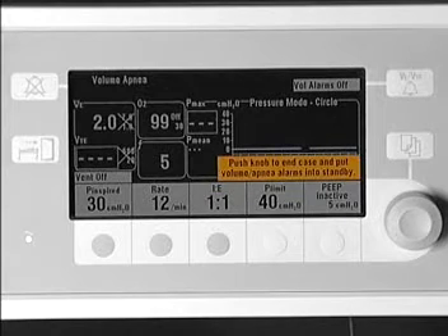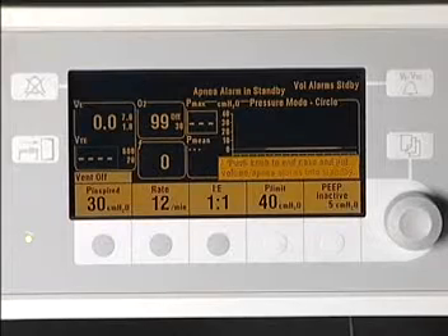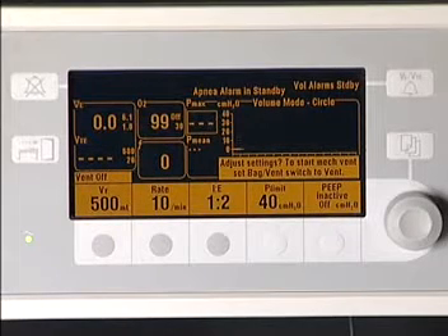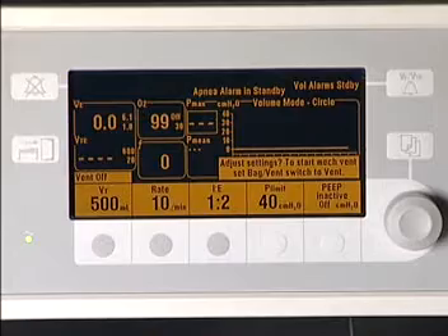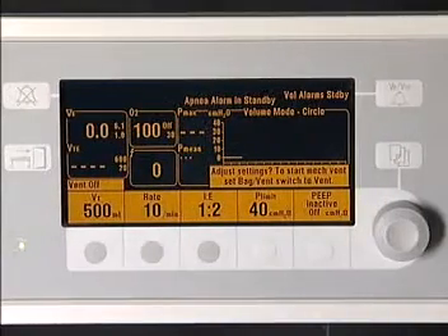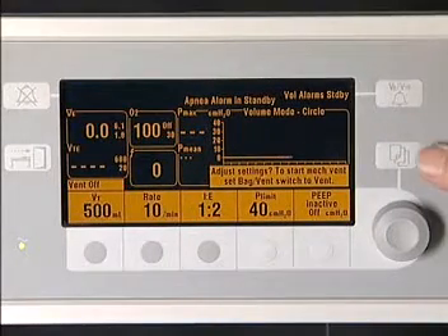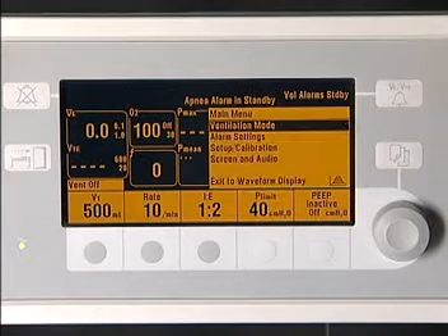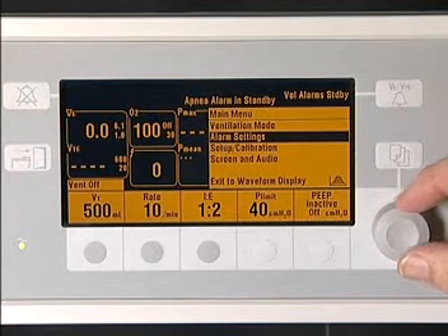The end case key should be pressed and confirmed via the encoder knob at the end of the case. This places the system in standby, silencing apnea alarms, etc., which will occur if the case is not ended. The settings and mode will return to the last case or to the values and the mode chosen as facility defaults when the machine was installed. If the machine is left idle for 10 minutes, it will automatically move to the end case configuration.